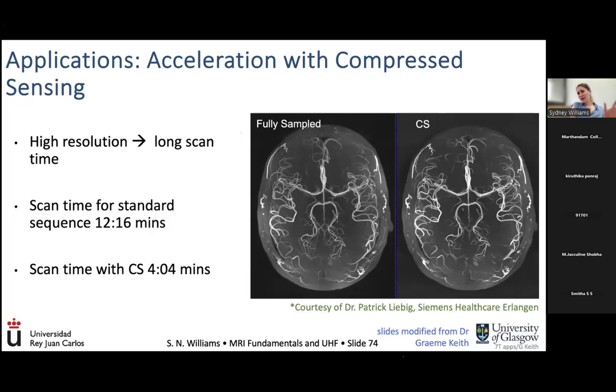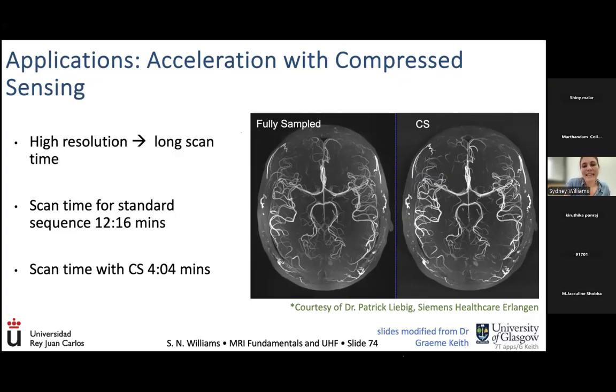Again, I talked about this parallel imaging capability that we're afforded with ultra high field. It really complements the high resolution that we get with ultra high field, because when we have that high SNR and higher resolution, we could take a very long time scanning. On the left, we show this really nice MRI, but what you don't know is that it's actually taking over 12 minutes. And 12 minutes is a really long time for a single scan, when we'll probably have multiple in the same session.